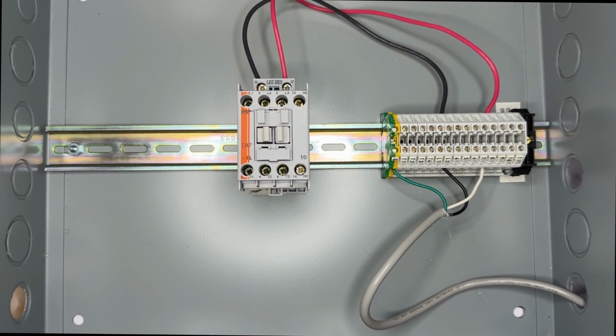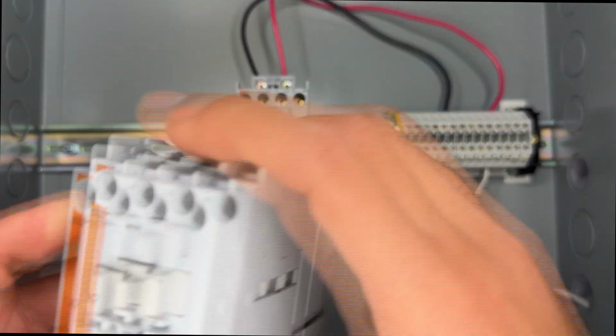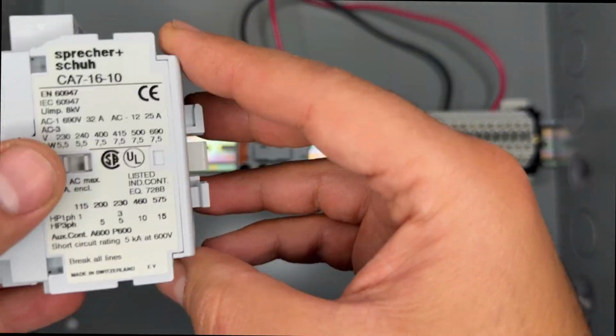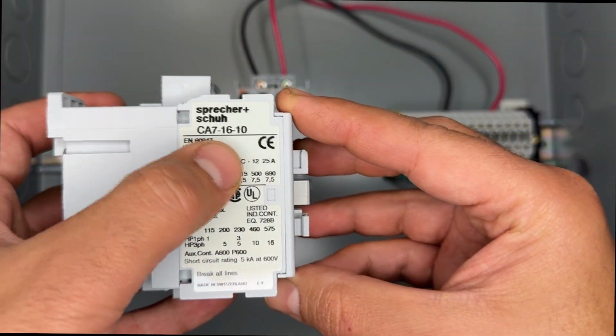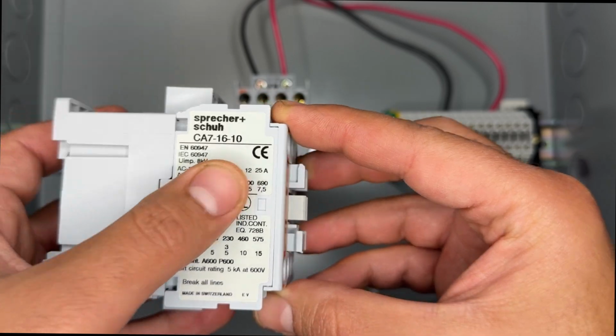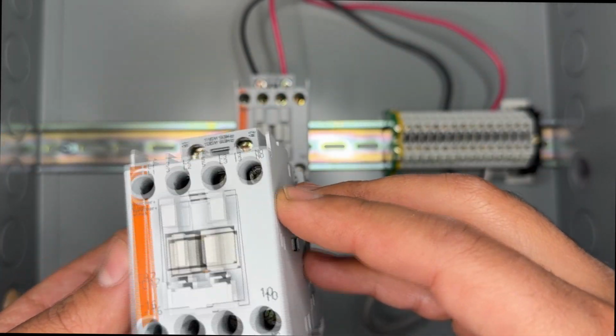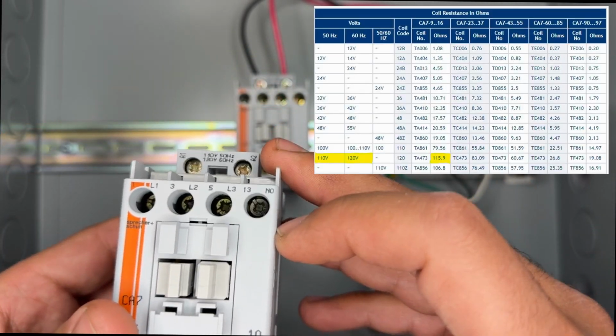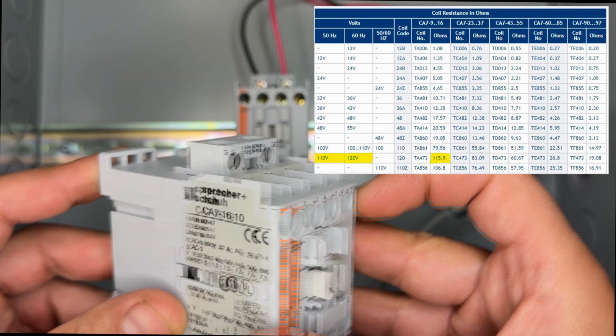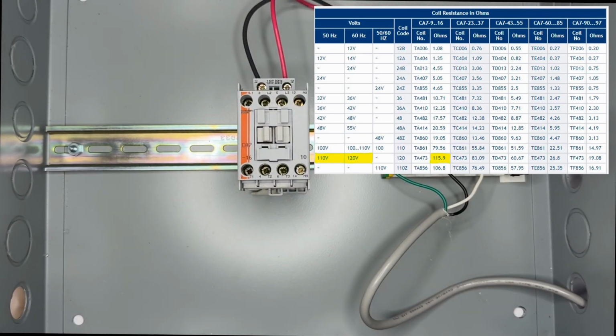The first test we're going to do is to check the coil resistance. Now in order to figure out what value we should be looking for, you're going to want to look up the spec sheet for your contactor. So for this particular one, it's a CA7-16-10. And if we look at the spec sheet, it tells us that the coil resistance should be 115 ohms. So let's go ahead and test that out.